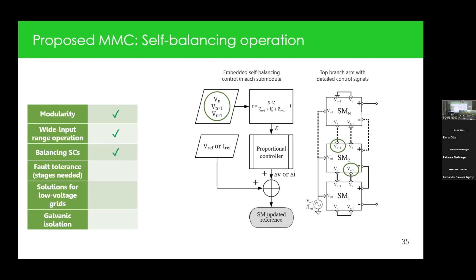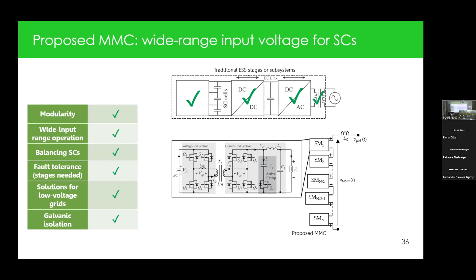So we have a system that reduces the many stages needed in the traditional energy storage system. We have a system that can achieve the balancing, the DC-DC conversion, the DC-AC inversion, and because we have the high frequency transformer in the submodules, galvanic isolation as well. So we reduce the many stages needed to just a single stage, a single series arrangement. And the solution can be suitable for low voltage grid applications, with galvanic isolation as well.